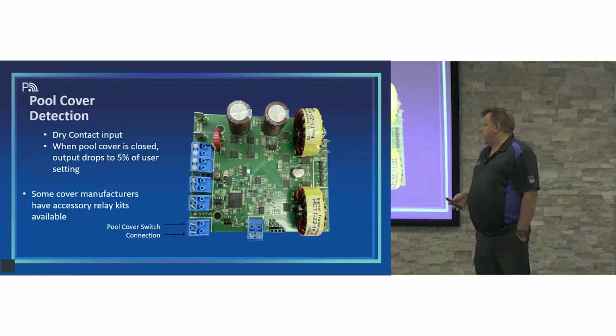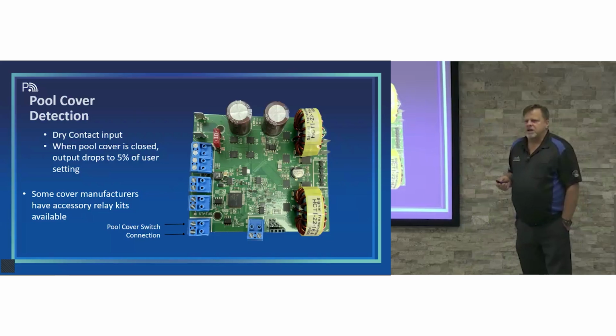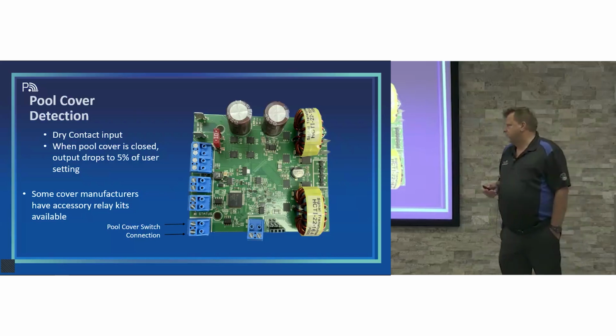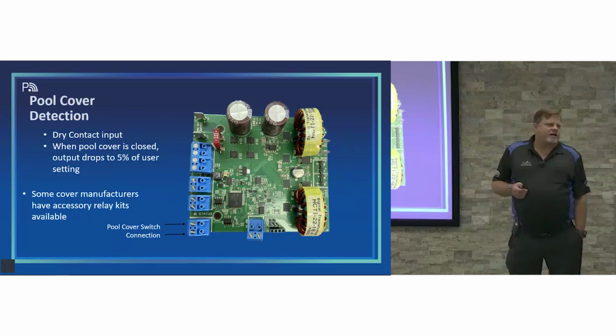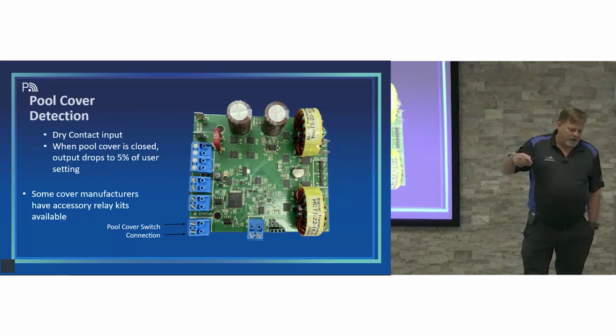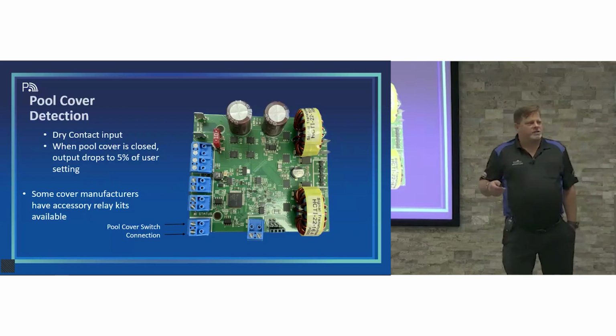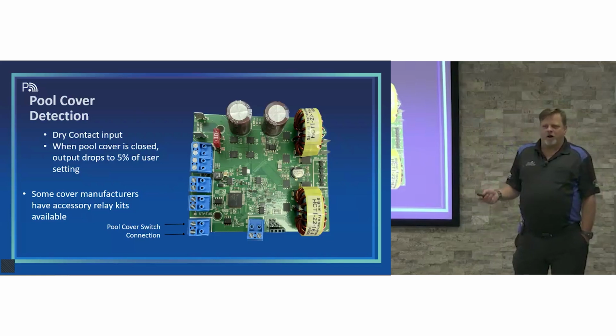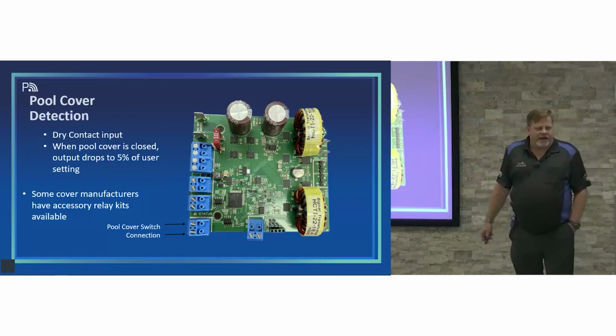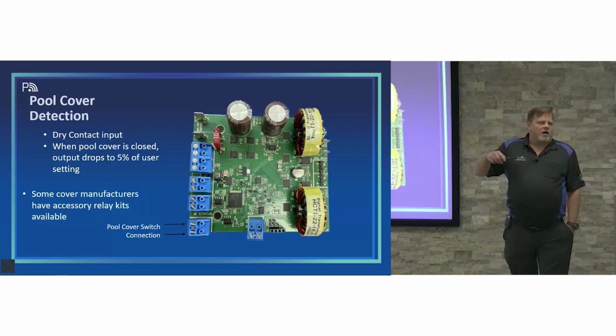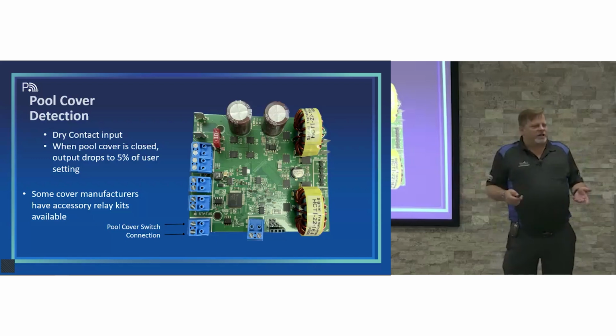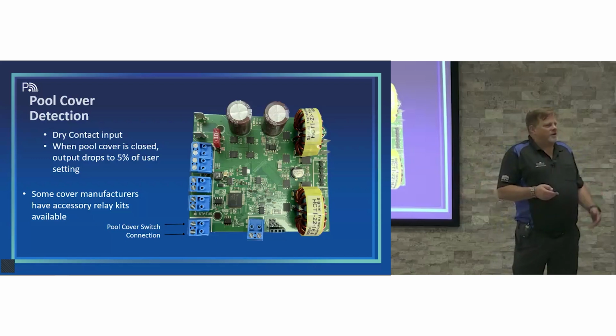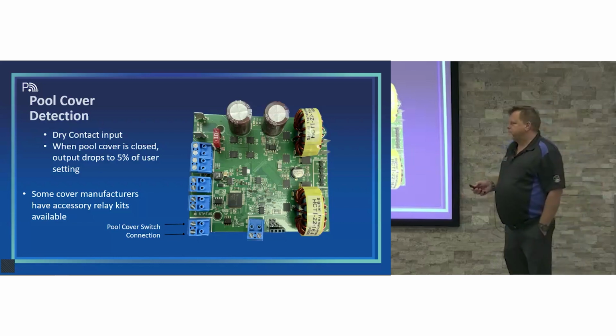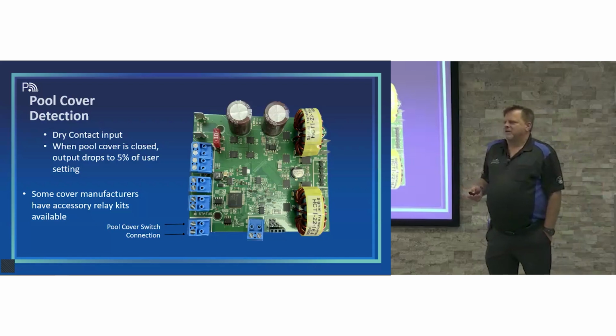This is the pool cover connection we were talking about. As mentioned earlier, it will drop the percentage down to 5% of whatever the original set point was when it's closed. This is a dry contact connection. A lot of your cover control motors operate off 220 or 115 volts, but it's not a wire from that 115 that provides the motor power to close or open the cover, it's the dry contact. So if you have a cover that only has high voltage going to it, you'll need a relay kit from the manufacturer. You need to call the manufacturer of that pool cover. I realize this is probably obsolete down here, I don't know of any automatic pool covers in Florida, but they're pretty big up north and out of state. Those relay kits typically have to be installed during construction.